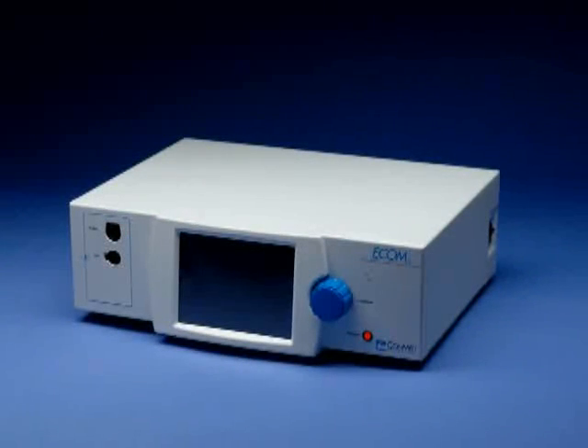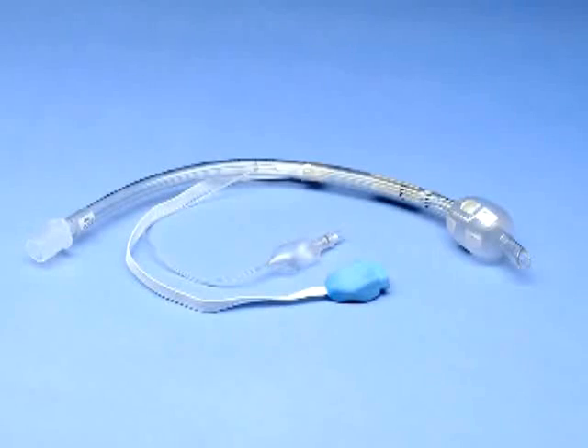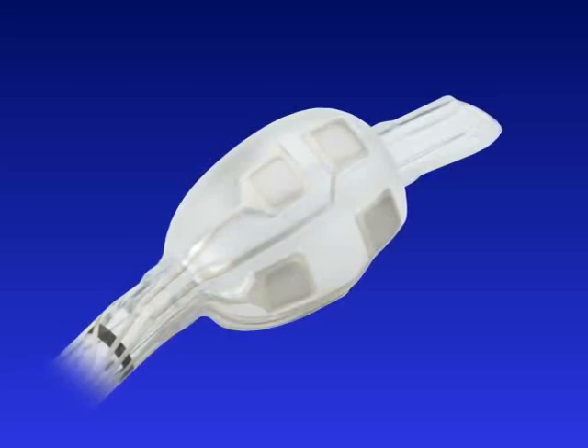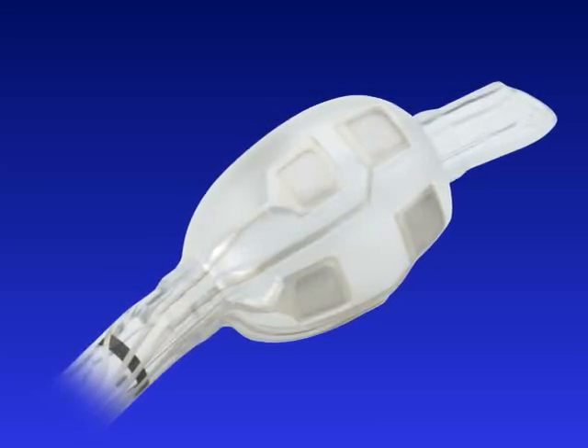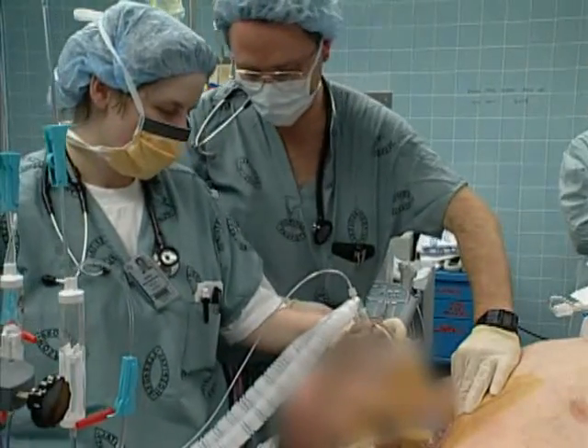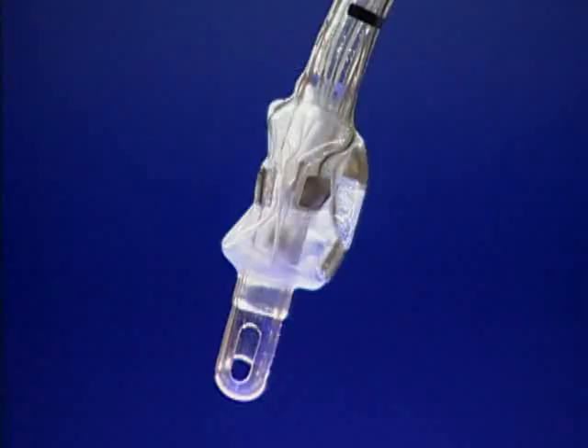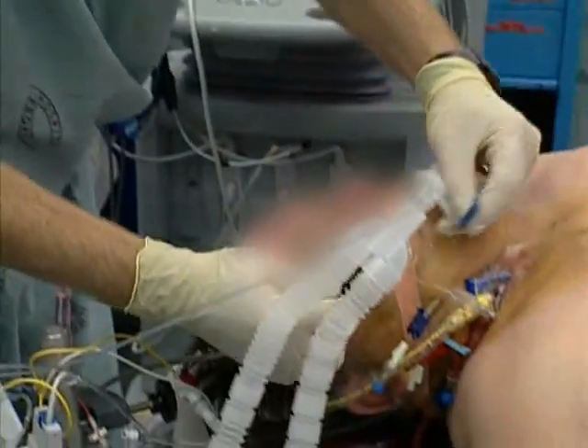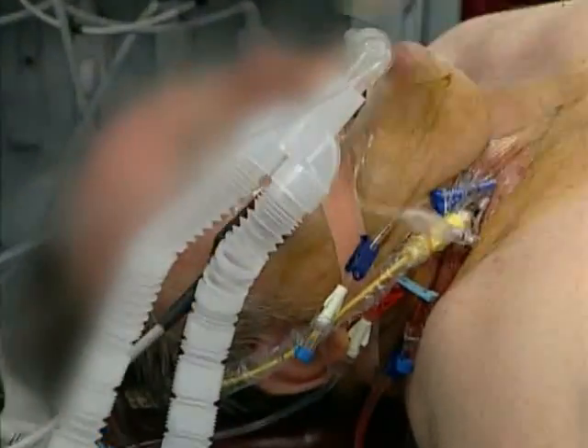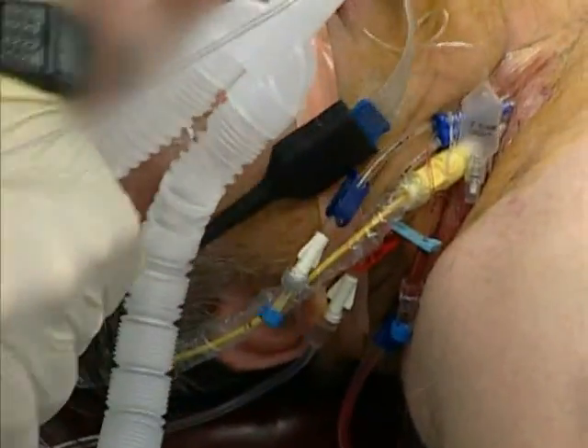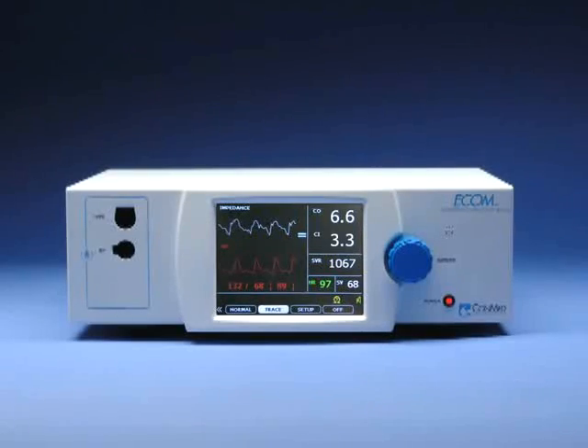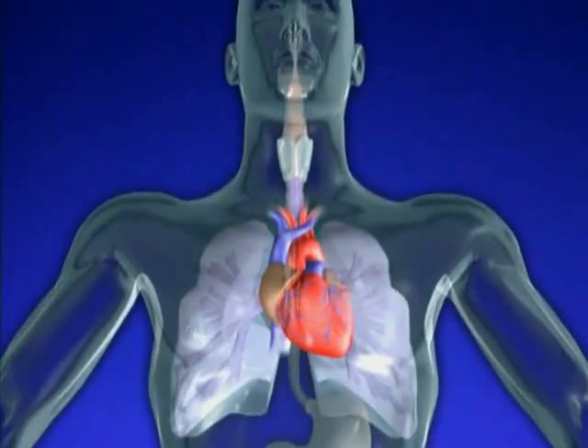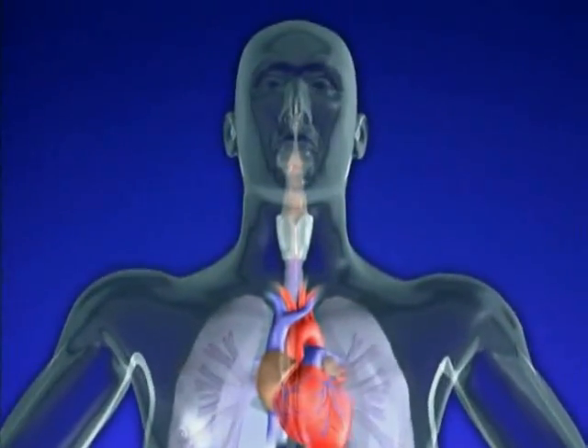The ECOM system consists of a monitor, cable, and endotracheal tube containing 6 electrodes on the cuff and a source electrode on the shaft. The endotracheal tube is inserted using standard techniques. Once the cuff is inflated, the tube cable is connected to the monitor, and real-time continuous cardiac output as well as other hemodynamic parameters are displayed. The following animation demonstrates the use of the ECOM system and the principles of impedance cardiography.